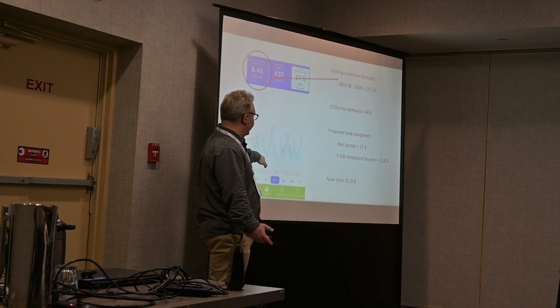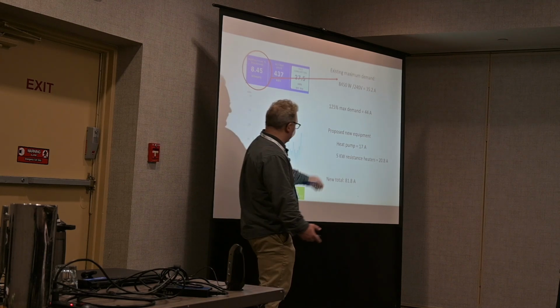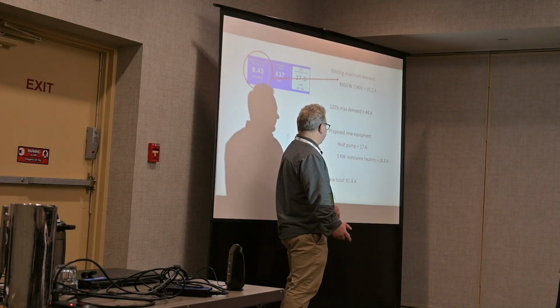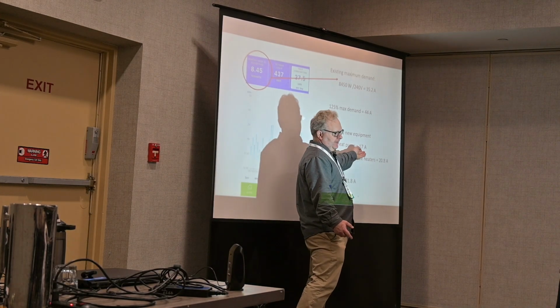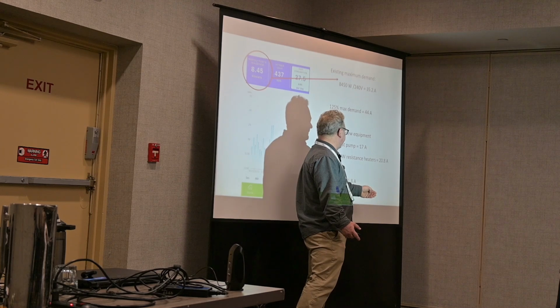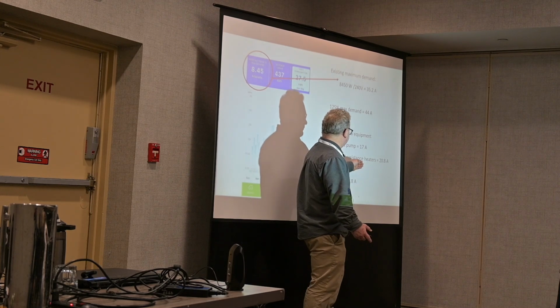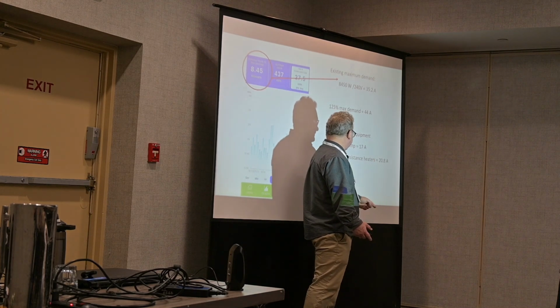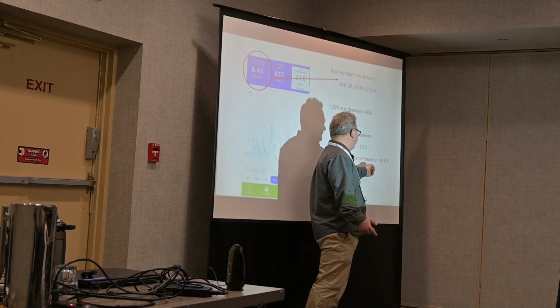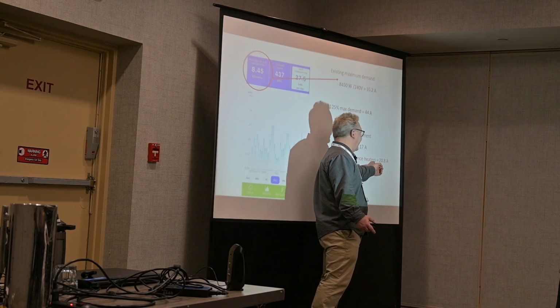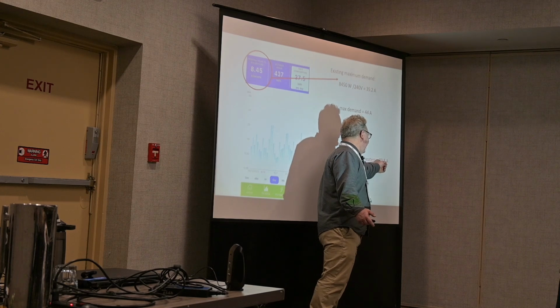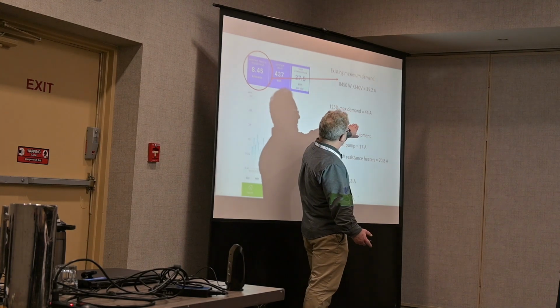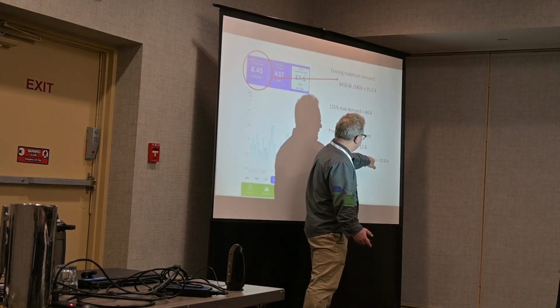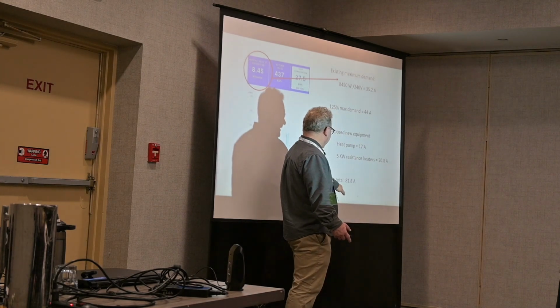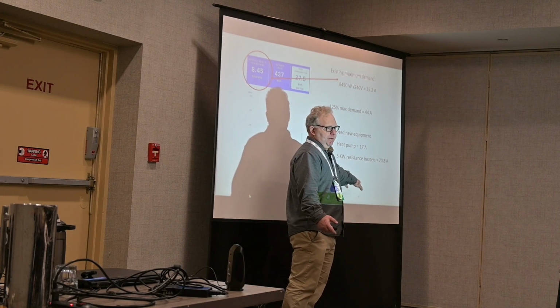But if we're removing the existing heating equipment and putting in a heat pump, we know from the submittal that, say, this heat pump has a rated load amps of 17, and we're also putting in a 5 kilowatt resistance heater. I convert that 5 kilowatts to amps. So with the existing demand plus the new demands, I can see here I am at 81 amps.